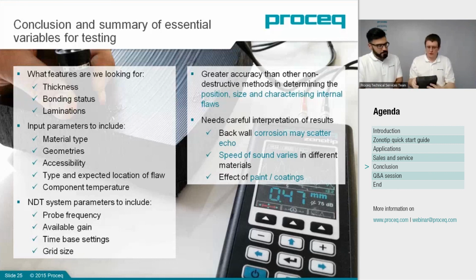Now, what you would usually suggest is, because this particular plastic is attenuative, to use the lower frequency probe. What we ended up using was the twin crystal higher frequency probe, because it had better resolving power from the back wall to this. And yes, then we solved the problem. And that goes to show that a lot of the time, the material dependency dictates that you really have to try different transducers physically to see which one fits better. And there's really no one solution to all thickness checking.